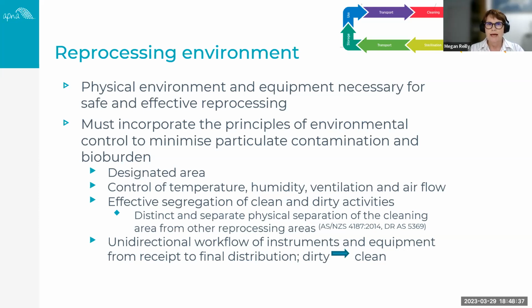So the standard requires that you have a designated area for reprocessing, that you take into account some of those environmental conditions such as temperature, humidity, ventilation and airflow, and we'll talk a little bit about that soon, and that there is effective segregation of clean and dirty activities. Now, currently in 4187, but also in the new draft standard, we will need to be thinking about transitioning to distinct and separate physical separation of the cleaning area from other reprocessing areas. So we just again need to be aware that there may well be changes afoot in terms of the environment.